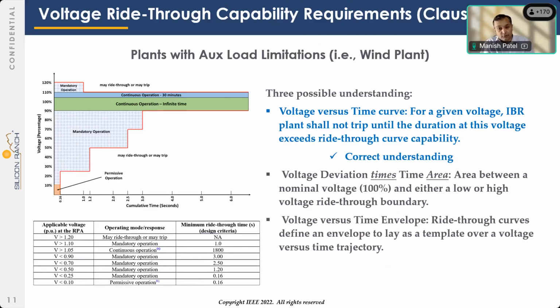The standard goes on to explain there are three possible interpretations of this table and a figure. The standard tries to convey that the correct interpretation is that this is a voltage versus time curve. For a given voltage, the IBR plant shall not trip until the duration at this voltage exceeds the ride-through curve capability. This is definitely not voltage deviation multiplied by time as an area integration, right?